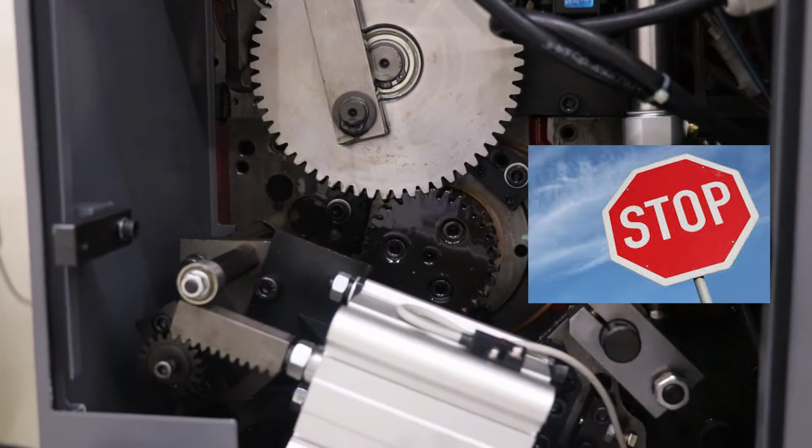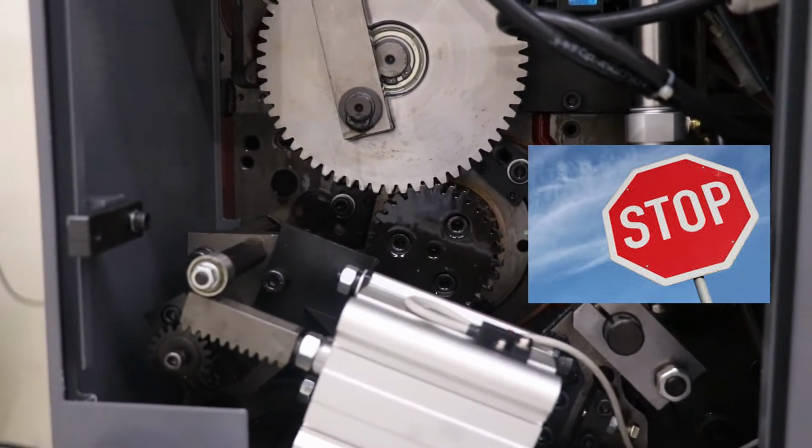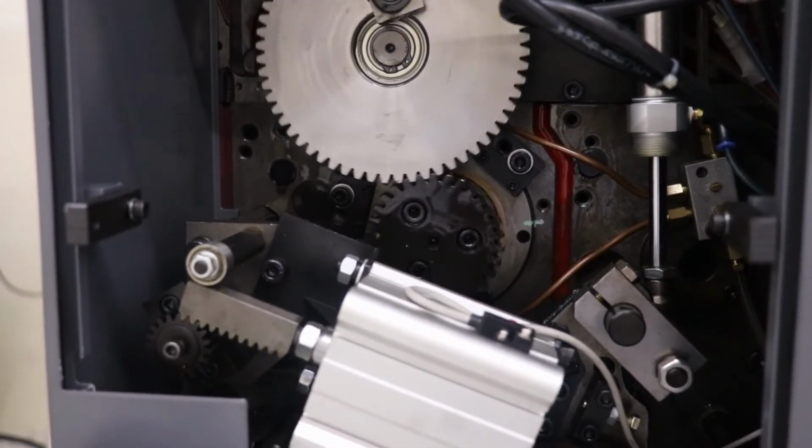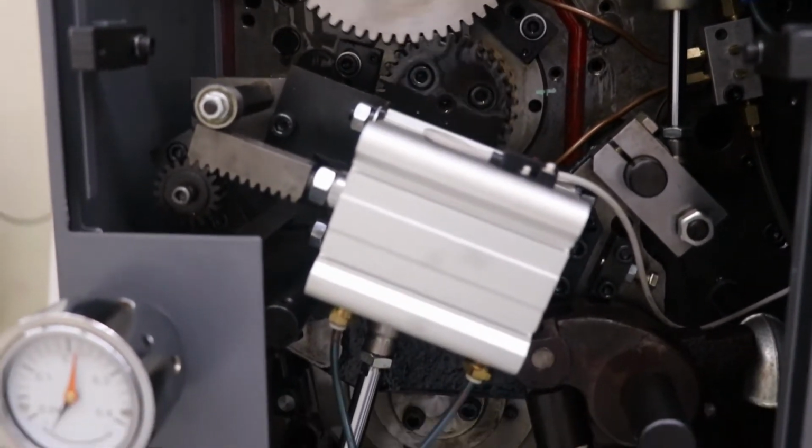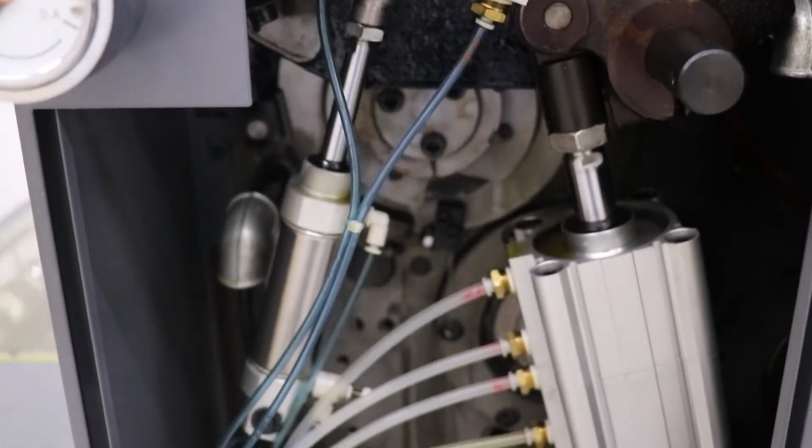As an example, if a stopping action requires 30 seconds to complete, then to figure out your duty cycle, you would divide 30 seconds by 120. This assumes that a stopping action happens every 2 minutes or more.